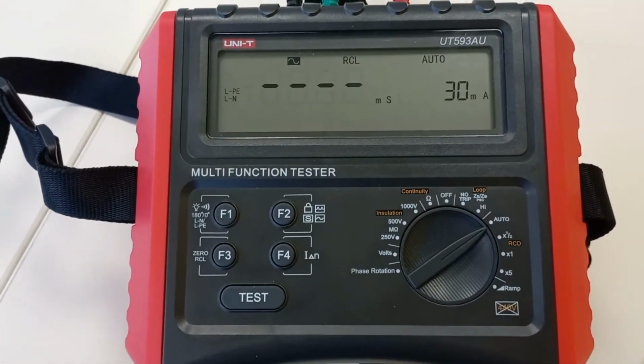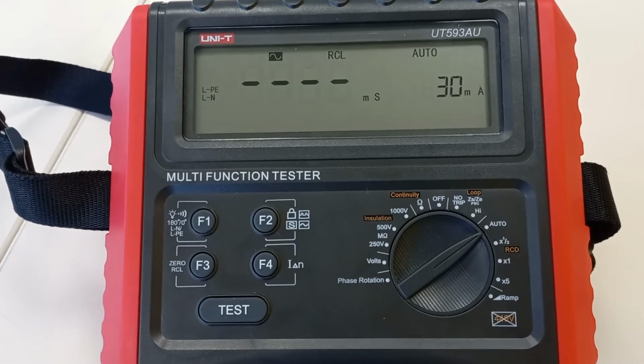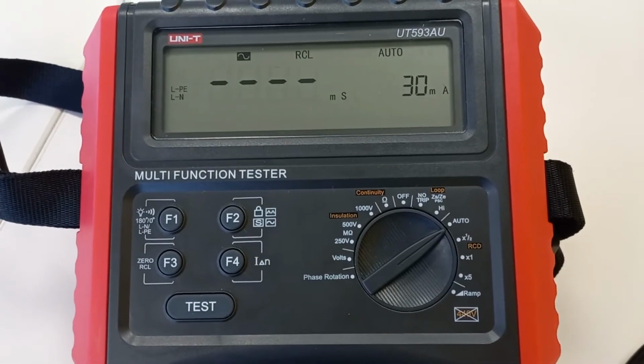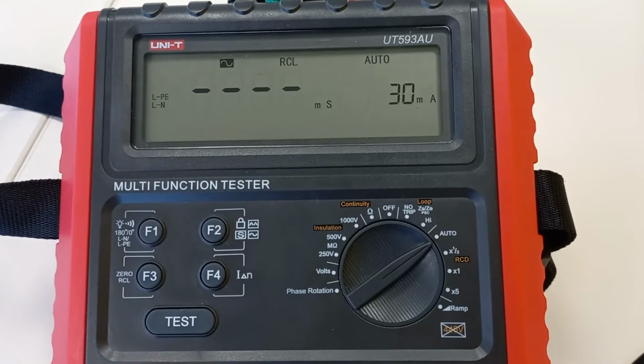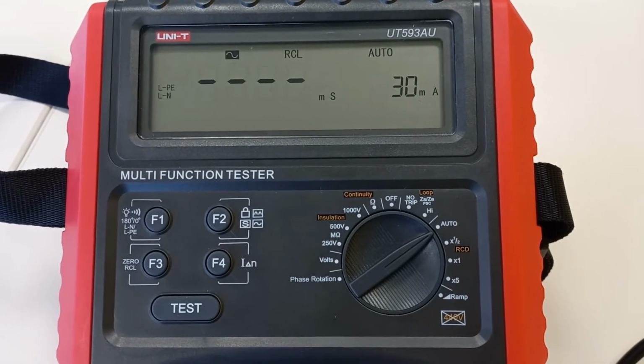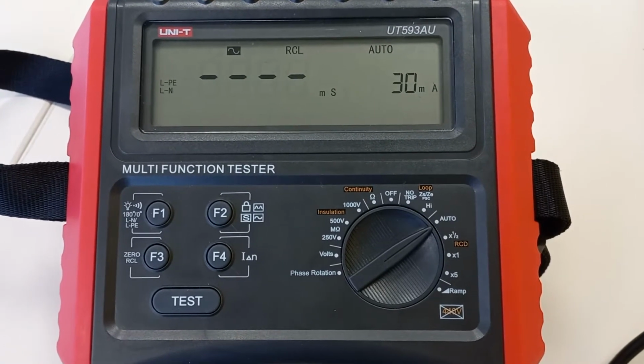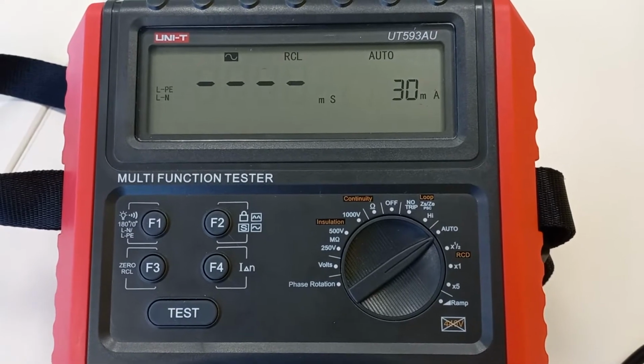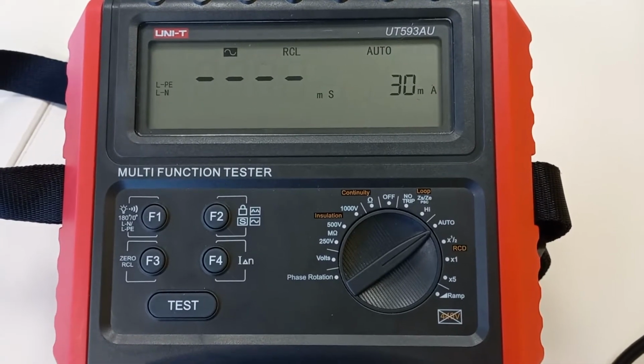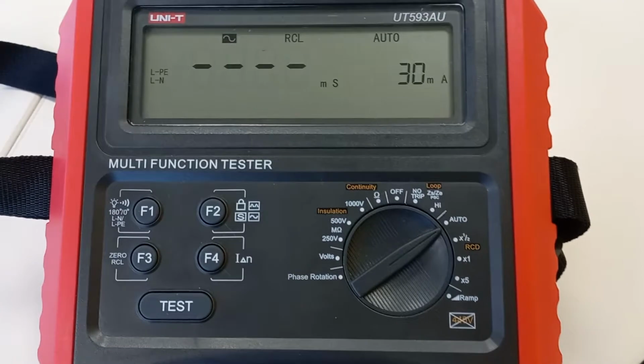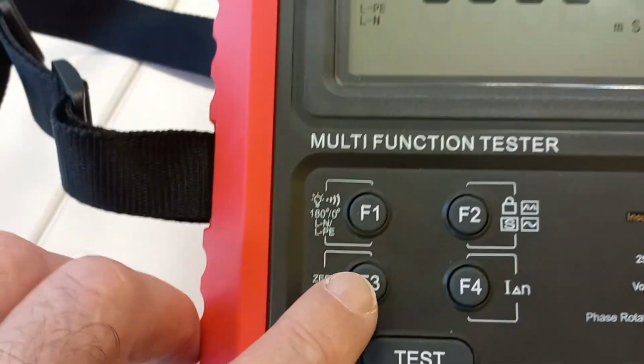The test it carries out is at half the rated leakage current, where it should not trip out, because that would be regarded as nuisance tripping. Then at 1 times the leakage current, which would be 30 milliamps, and then at 5 times the leakage current, which would be 150 milliamps. So now we're going to go back through and recall the readings.